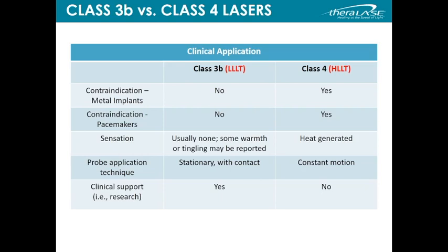The class 3B lasers usually don't produce any sensation. There may be some warmth or tingling that's reported by the patients, and the probe application technique is stationary. You just keep the probe in direct contact with the skin, whereas with a class 4 laser, because of the heat generated, you have to keep the probe in constant motion.